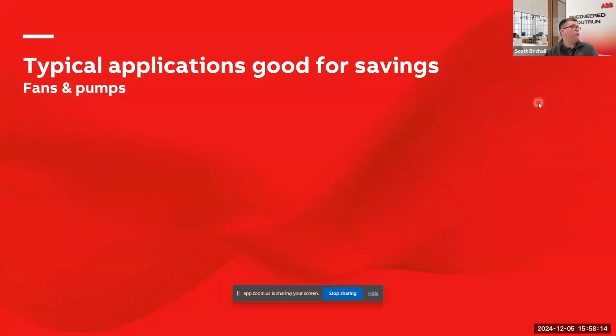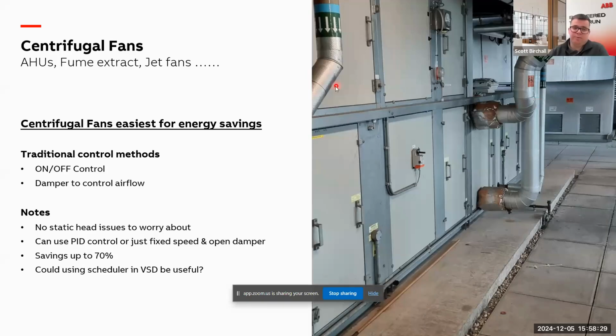Next, I'm going to look at typical applications good for savings. What are the ones that you should be looking for? The low-hanging fruit, the ones you could really do something with to start. Fans and pumps are the typical ones. Centrifugal type fans are the easiest for energy saving because of variable torque loads. As you reduce the speed, the energy savings cube.